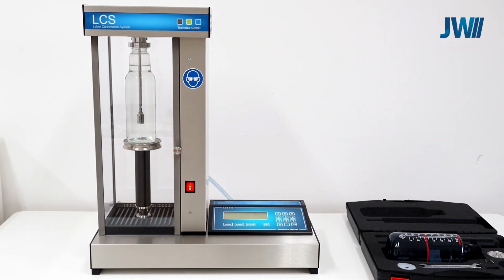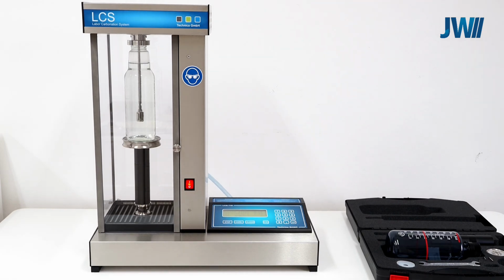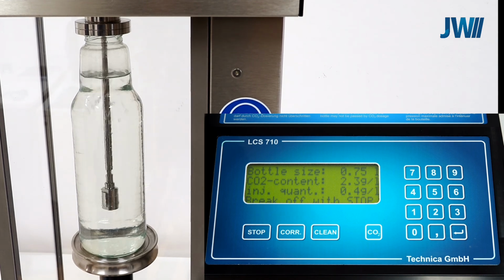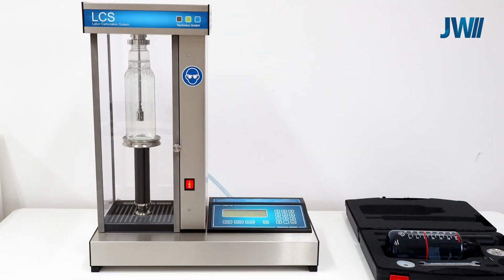At the start, the device flushes the air at the top of the bottle to remove any foreign air. Next, CO2 is dosed. During the process, the progress is displayed on the screen. The device then vents the bottle, first releasing the pressure and then fully venting it. Once finished, the door unlocks and a signal tone sounds.